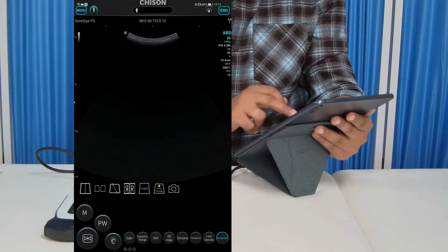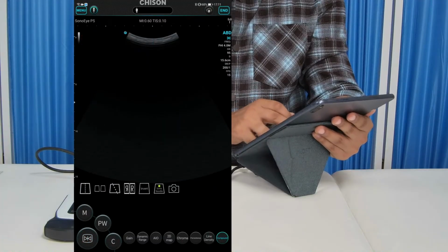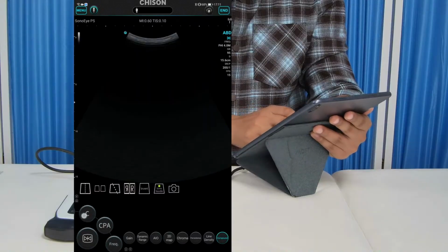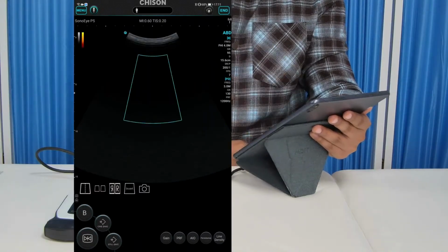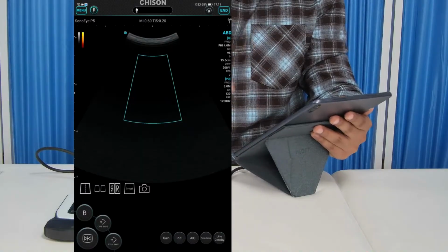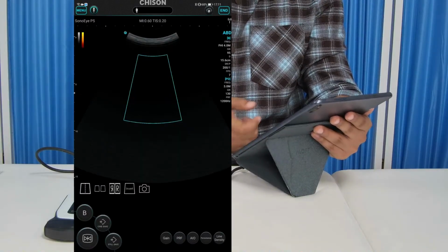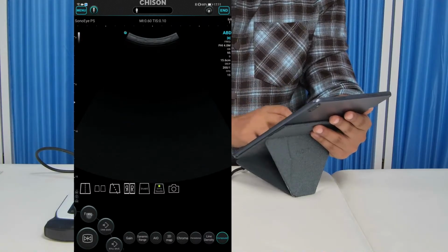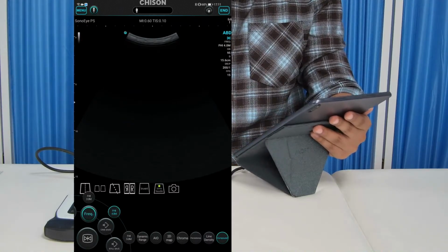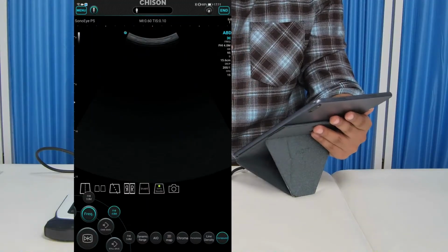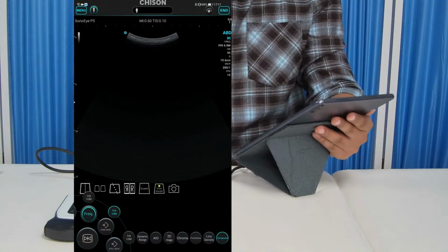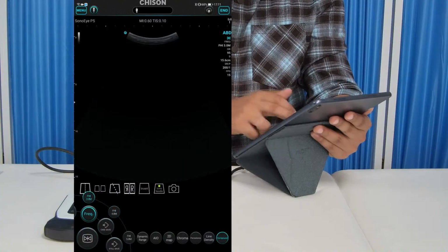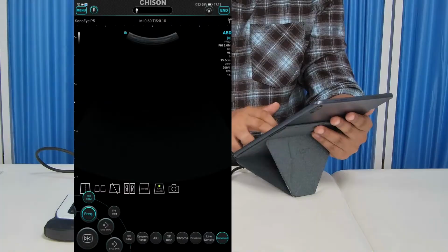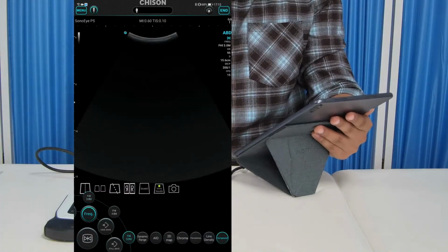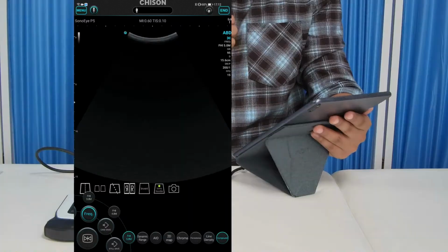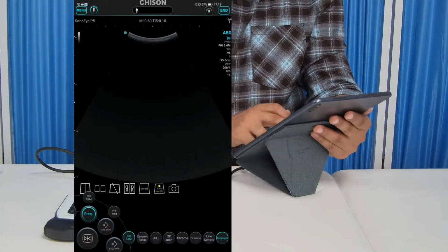Similarly, we have multiple modes available in this one. We have color mode, we have pulse wave, we have M mode, and we have color power angiography. So you can choose the power Doppler as well for better visualization of superficial vessels. We also have the frequency option to adjust the frequency as per your needs. If you need the lower frequency to visualize the deeper structures, you can choose 3 megahertz. If you need the higher frequency, you can choose 5 megahertz. We are using the harmonic frequencies over here to provide you better imaging in a handheld ultrasound.